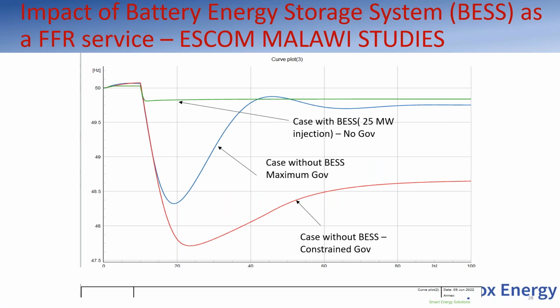Here I'm showing the relationship between BESS and governing response in terms of frequency response. If you look at batteries, the green one is a battery that is responding. In the Malawian system, it was about 25 megawatts of battery injection, and there was no governing at all, but it managed to arrest the frequency very high, above 49.5, around 49.8 or so.